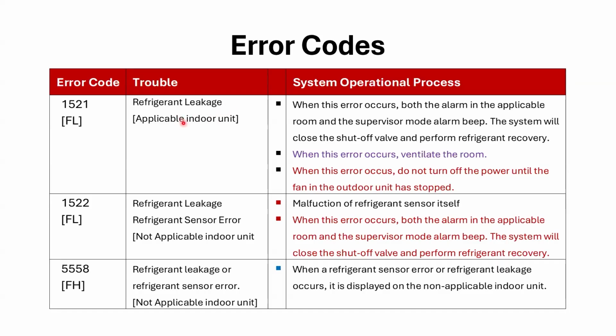Refrigerant leak. So talking about the indoor unit, and so okay, here's the process. When this error occurs, both the alarm is applicable to the room and the supervisor mode alarm beep. That's coming up next here. So the system will close the shutoff valves and perform refrigerant recovery. So talking about Smart Multi, in the new Smart Multi outdoor units, we have electrically controlled shutoff valves in the outdoor unit on the vapor and liquid lines. And what the unit does when it detects a refrigerant leak, it's going to go into pump down mode and recover that refrigerant and then shut those valves and contain it in the outdoor unit. A little bit more information coming up on that. So that's what it's doing.